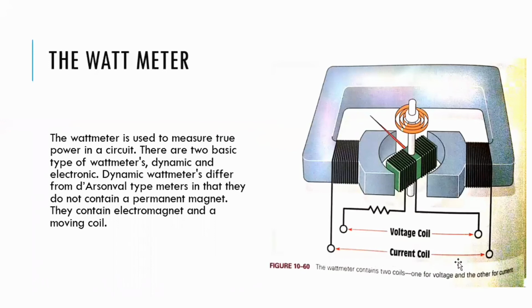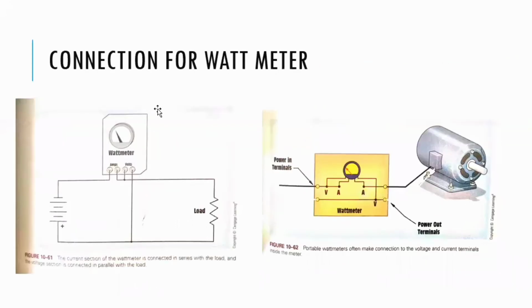They contain an electromagnet and a moving coil. Right? The current coil is the electromagnet, not a permanent magnet. And the voltage coil is right in the center between the current coil. And this is the spring which holds the moving coil in the zero position. And this is the pointer. This is the connection for a wattmeter.